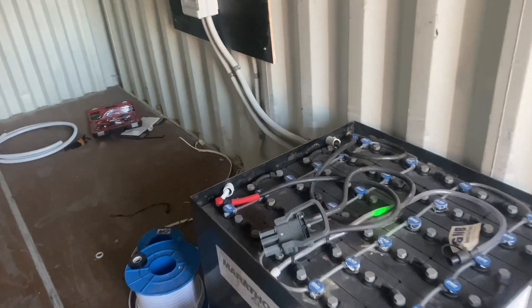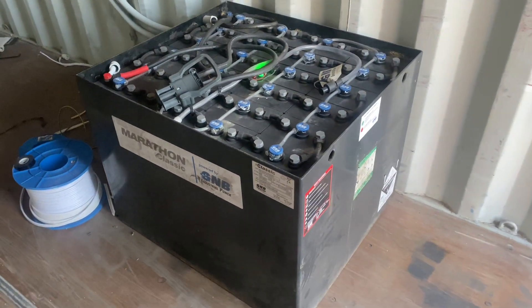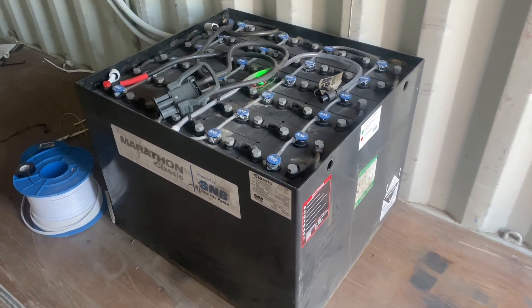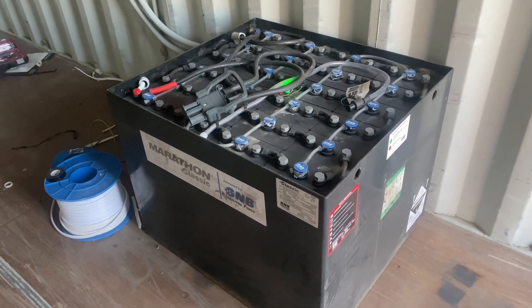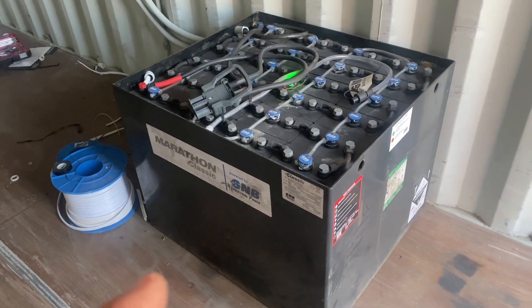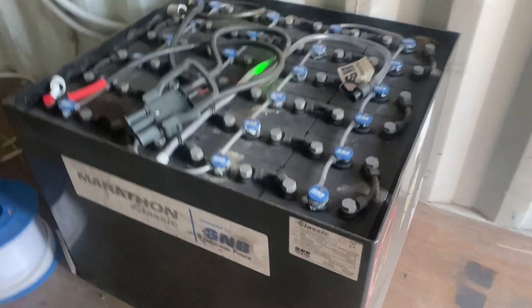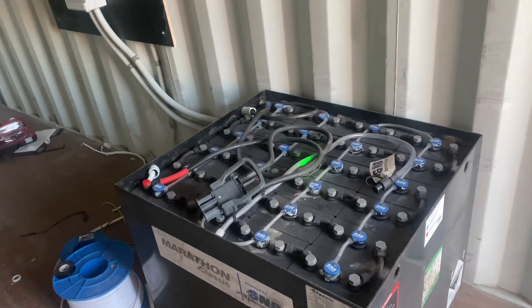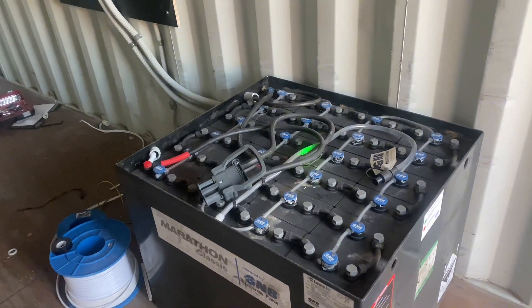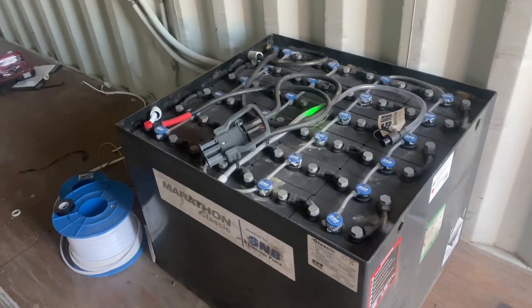G'day viewers. I've got to take a quick video of this one because it's quite different. Take a look at that — that is a battery bank out of a forklift. This particular client, in a previous business, purchased this battery bank as a replacement for an electric forklift. It's 48 volt, 750 amp hour, but it's lead acid so we can't use all that power. We can only use about half because you only want to discharge lead acid to about 50%. But that's a huge amount of storage.